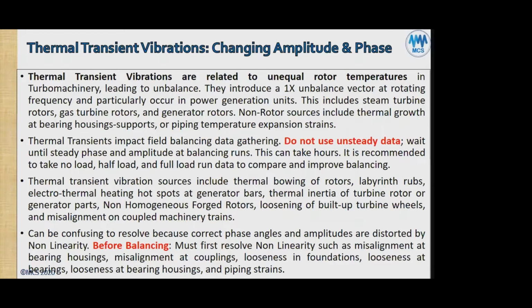Also, loosening of built-up turbine wheels. Built-up turbine wheels means where you have a shaft and the wheel is slid on with hopefully a shrink fit and typically a keyed connection. So it's not an integral rotor. And if these loosen, then they cause unusual vibrations, which will end up having a thermal component. And then you have misalignment on coupled machinery trains. This introduces thermal transient vibration also.